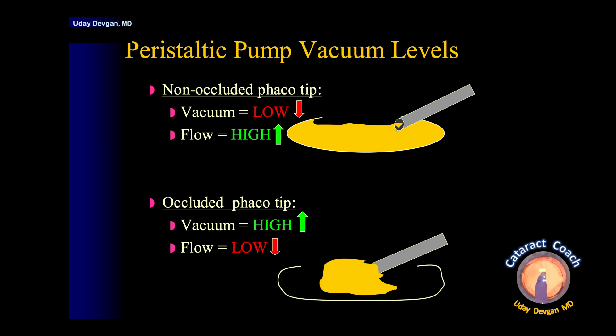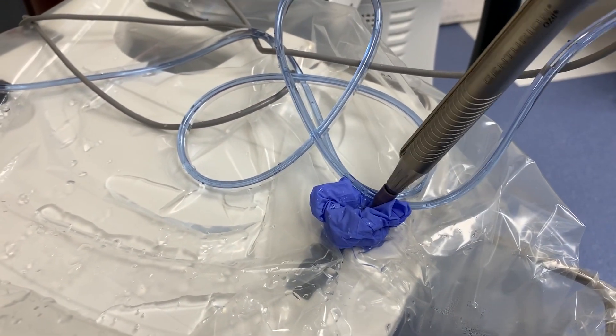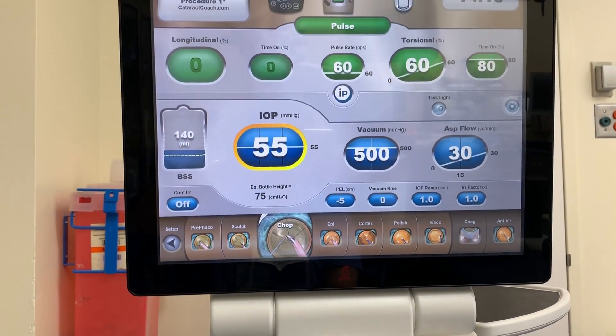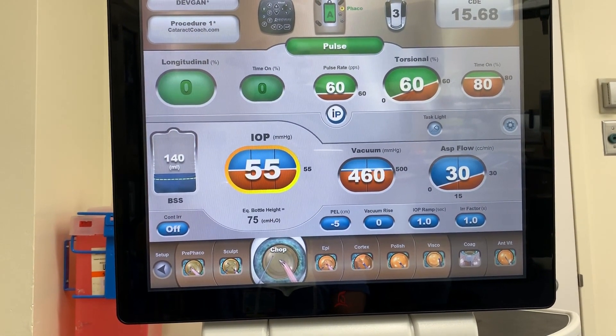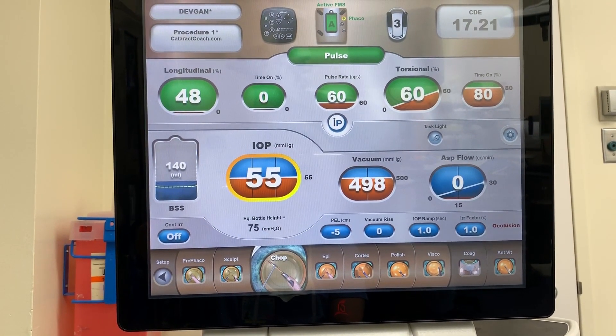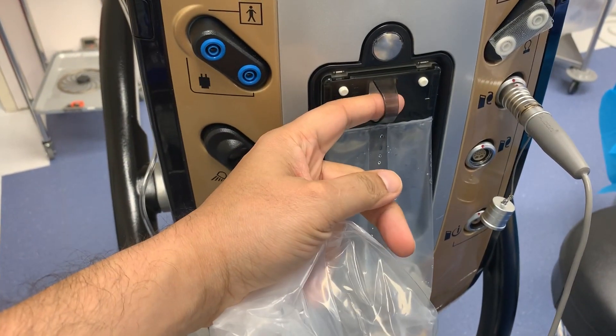Non-occluded means low vacuum and high flow. When you occlude the tip, the flow drops, but now you can increase the vacuum to your preset level. If we occlude the phaco tip completely, the vacuum keeps building and we can achieve our target vacuum. Occlusion is required for maximum vacuum on a peristaltic pump.